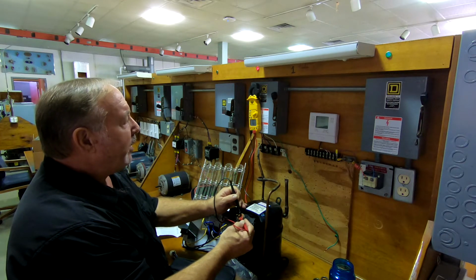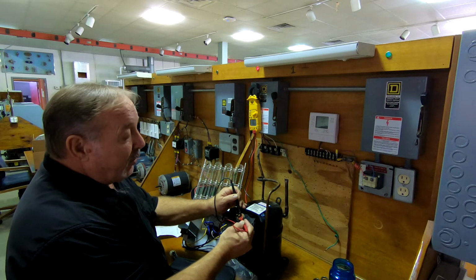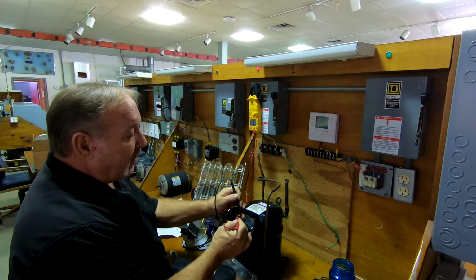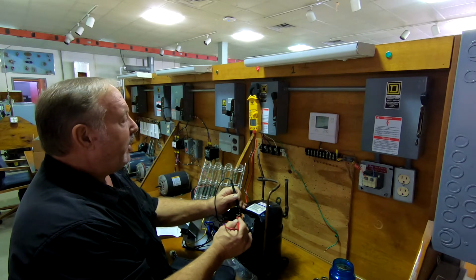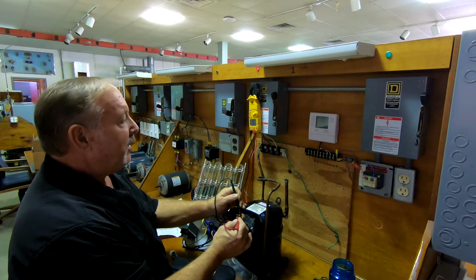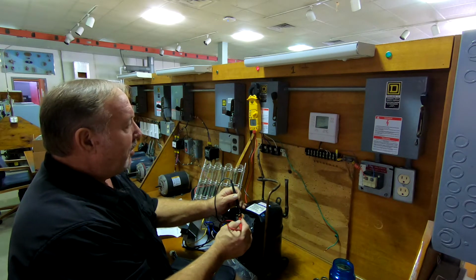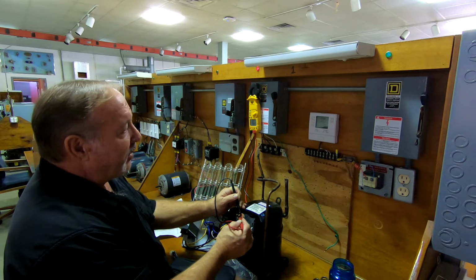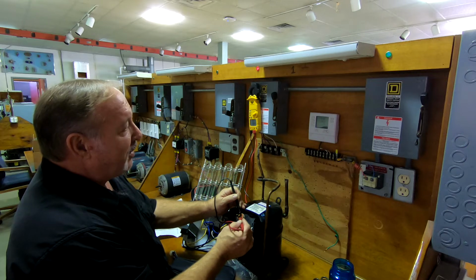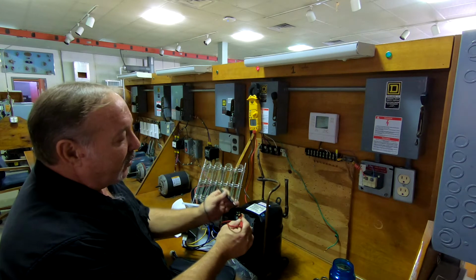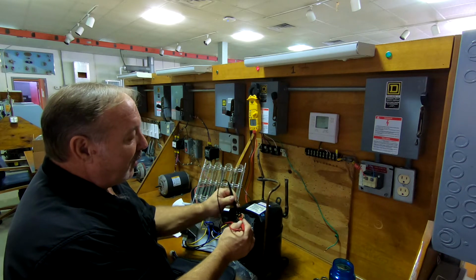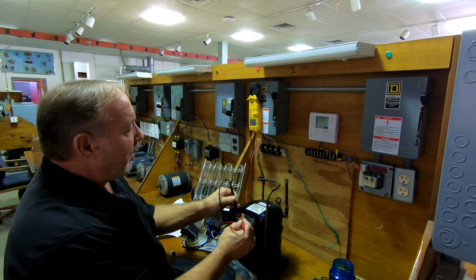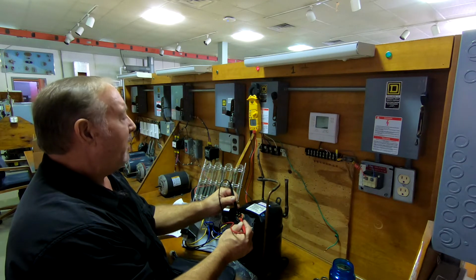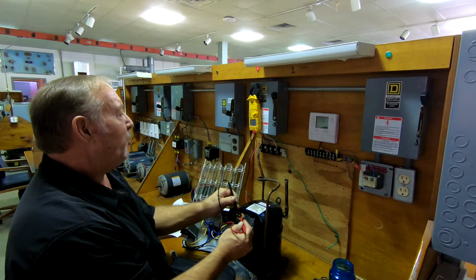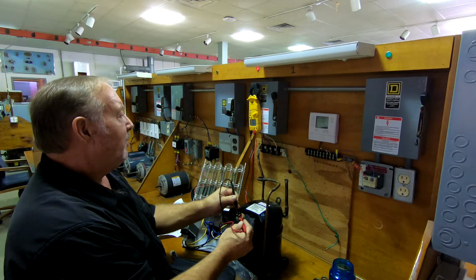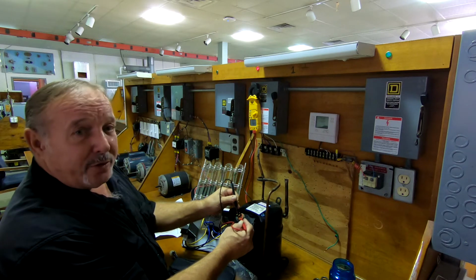So now I'm reading 0.6, 0.7. So those two are going to add. So we had 4.2, 4.3, and we had 0.5, so additive, okay, now it's 0.6, 0.7. So 4.3 and 0.7 should be about 5 ohms. So now when I go between start and run, we should see them add up, and what I have now is exactly 4.9, 4.8 ohms. So it holds true.